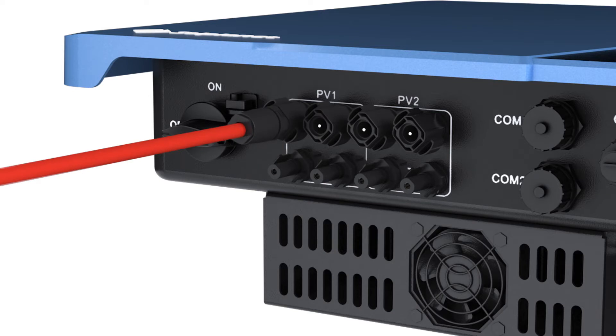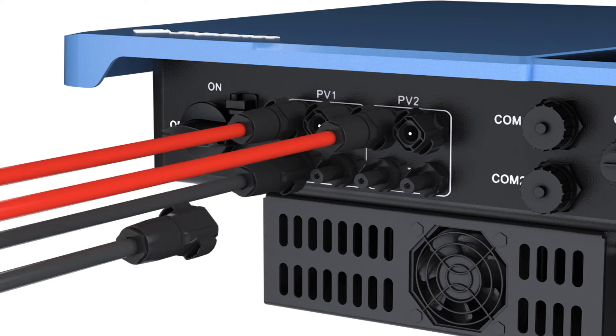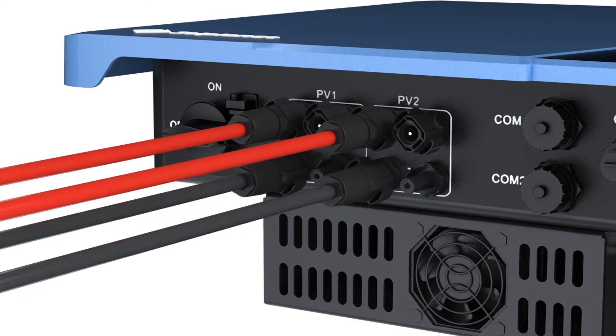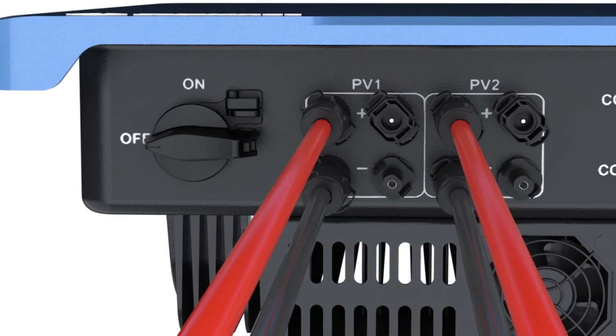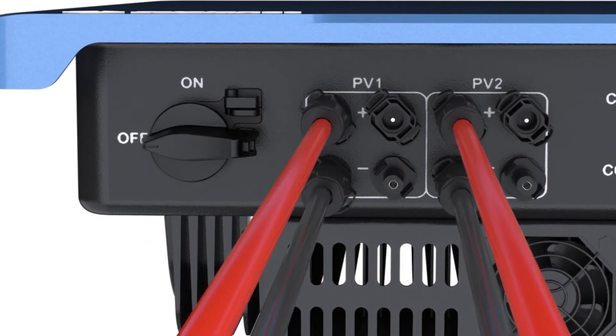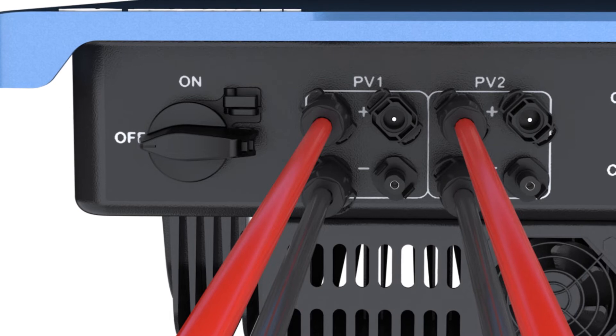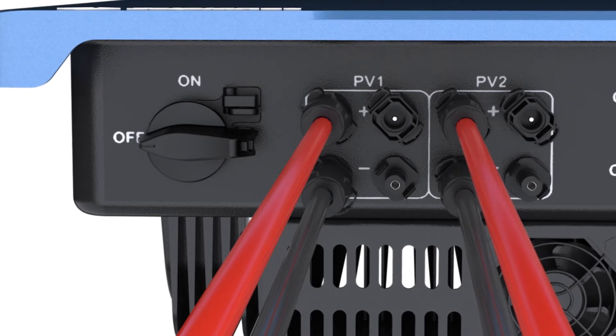Connect the assembled DC connectors to the inverter until they audibly snap into place. Ensure that all DC connectors are securely in place. Seal the unused DC inputs with sealing plugs so that moisture and dust cannot penetrate the inverter.